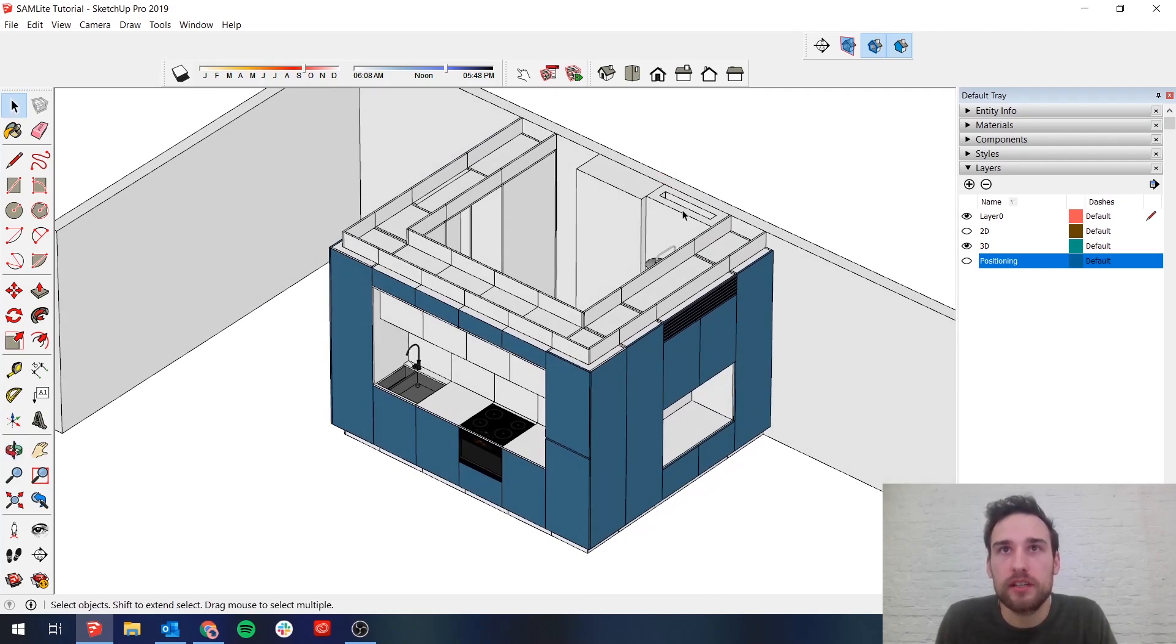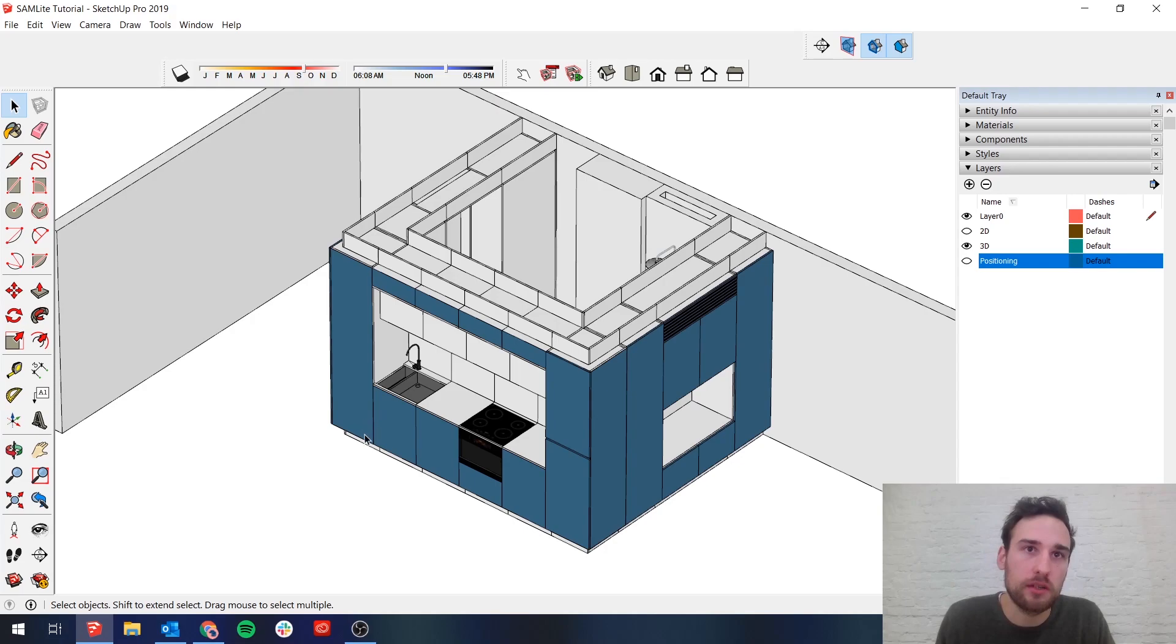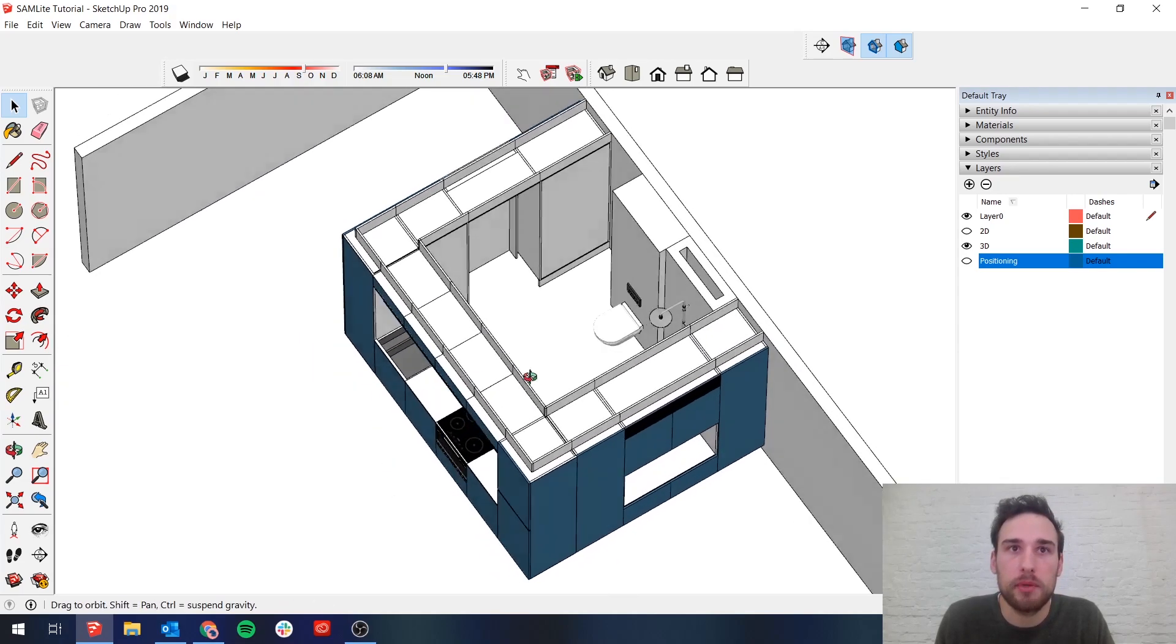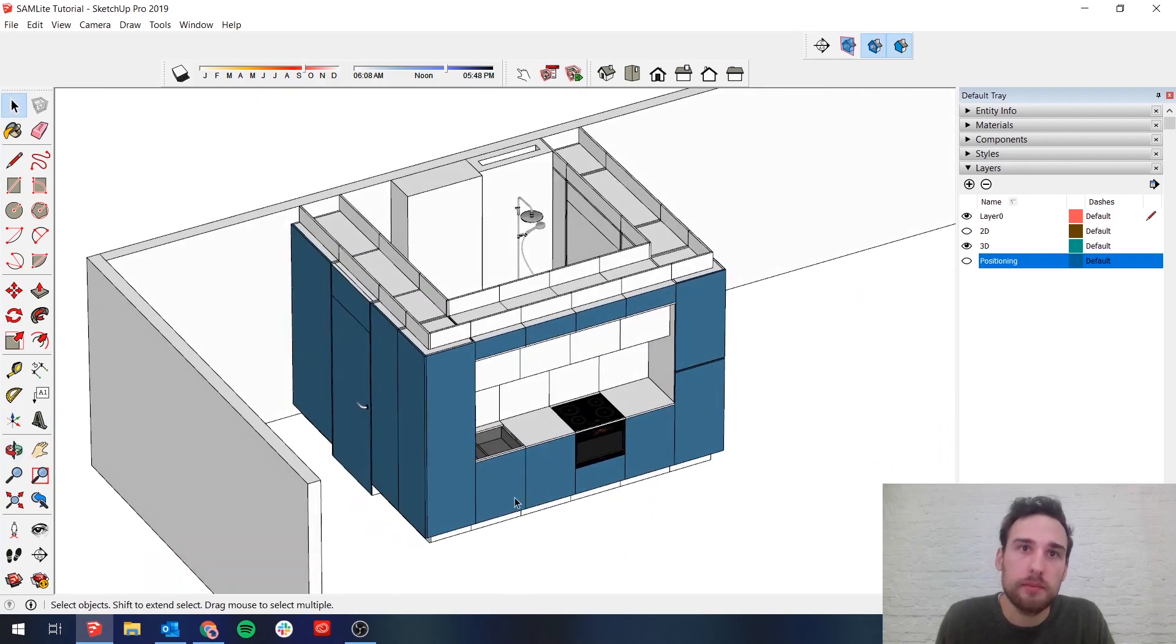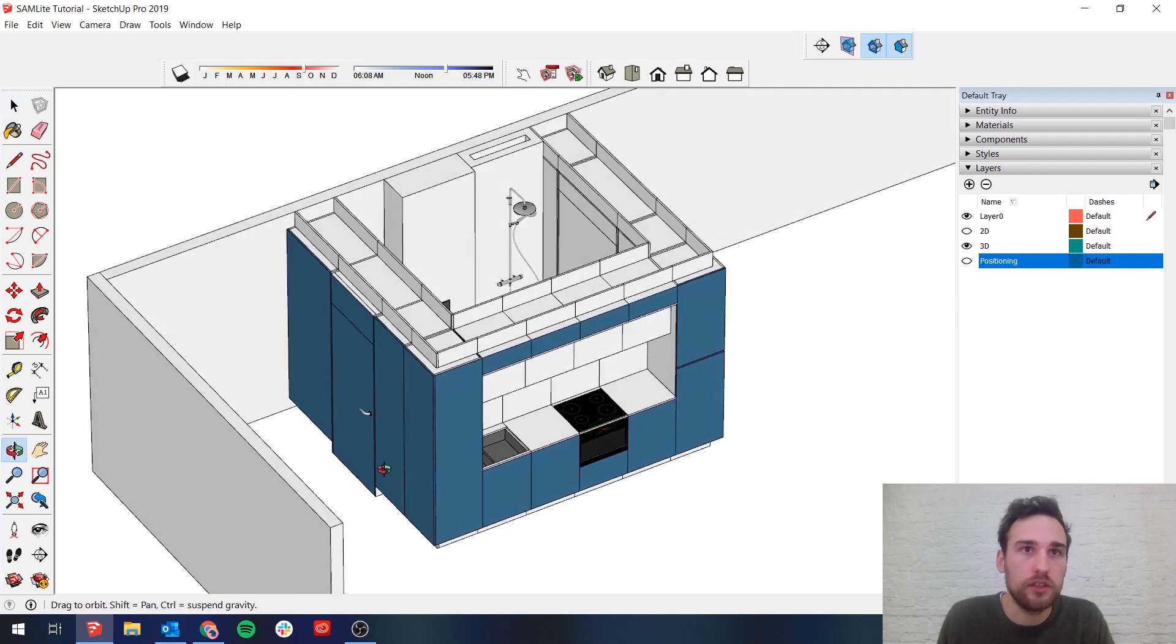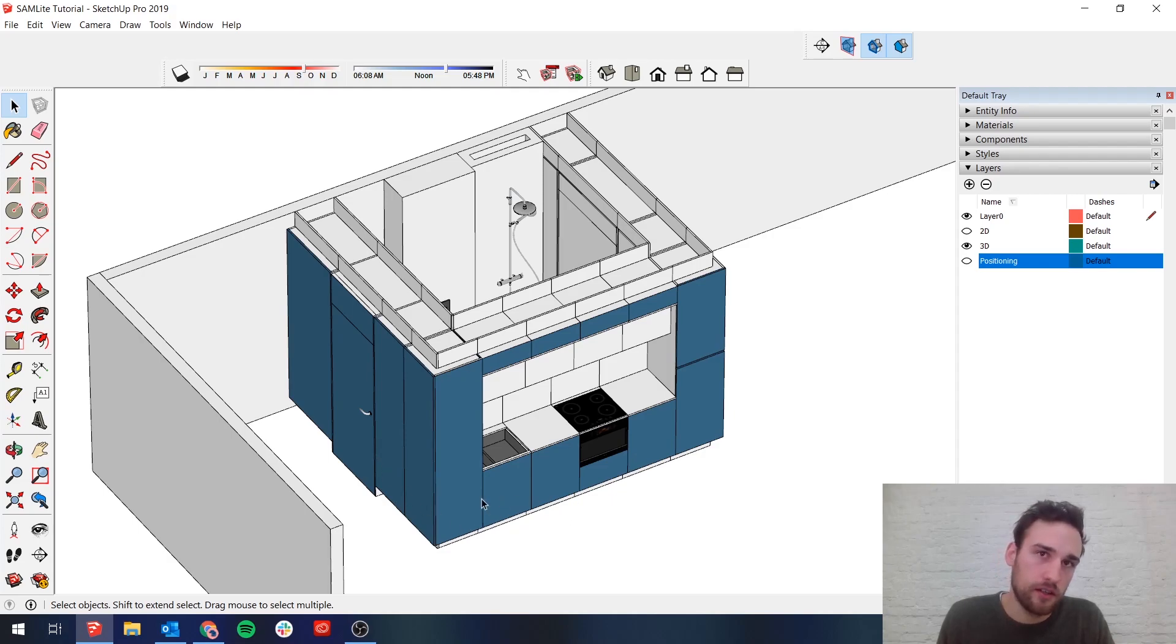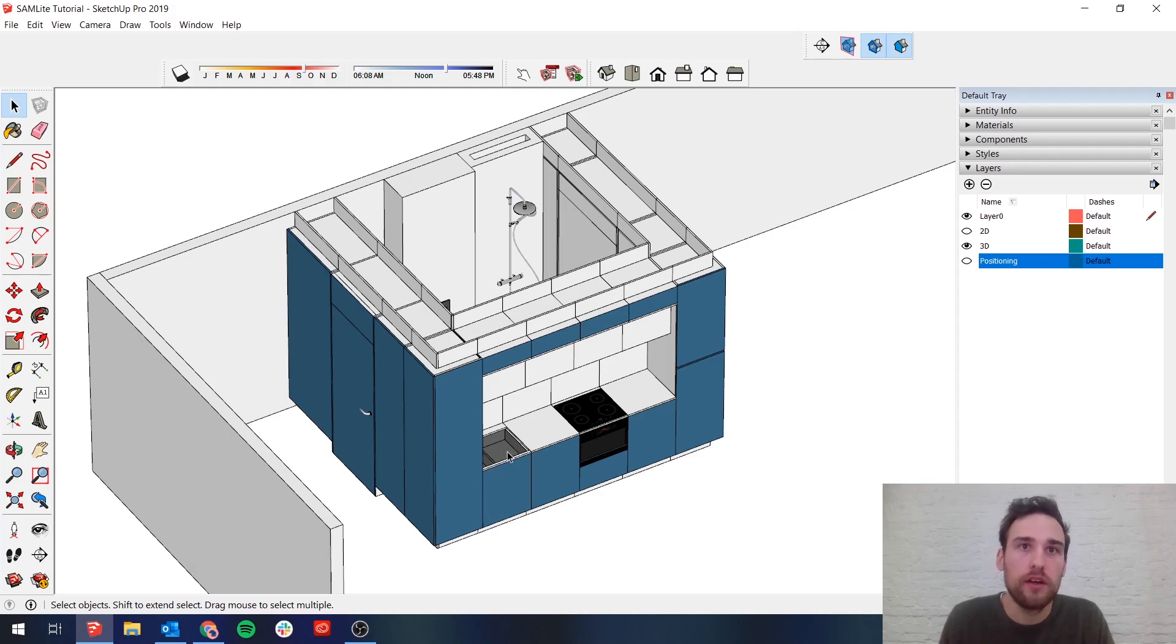Leaving from the technical risers of the shaft, you want to have a clear path for the sanitary piping running along the bottom, so that you can service this sink and the sink in the bathroom. Important to note that sanitary piping cannot go past a door, so keep this in mind when you are designing the SAM that the plumbing, the sink and anything else that needs to be supplied with running water is placed before a door.